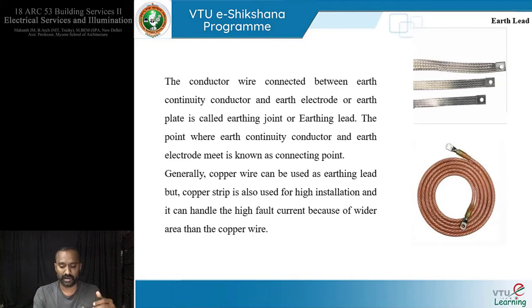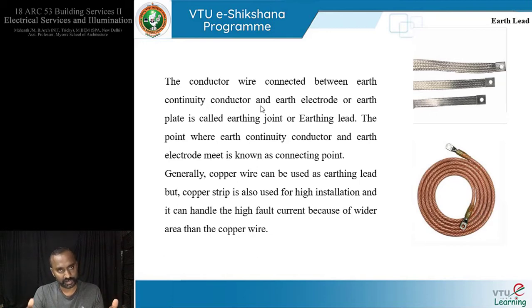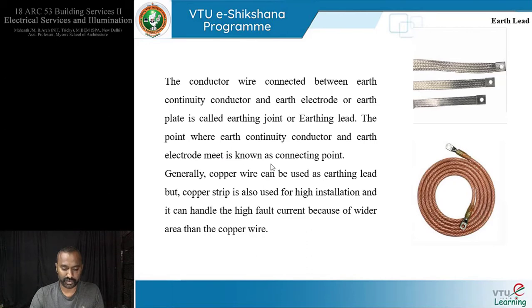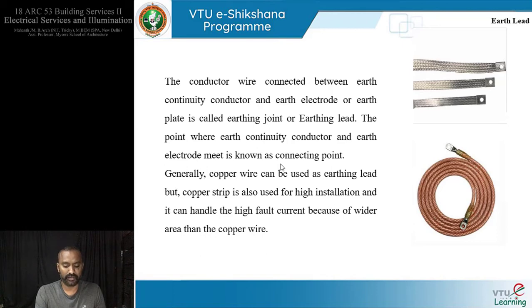The second component is the earthing lead. The earth wire comes and stops at a particular point, and then the earthing lead continues from there. The earthing lead is the conductor wire connected between the earth continuity conductor and the earth electrode. The point where the earth continuity conductor and earth electrode meet is called the connecting point. Generally, copper wire is used as an earthing lead, but copper strips can also be used because they handle high fault current better due to their wider area.